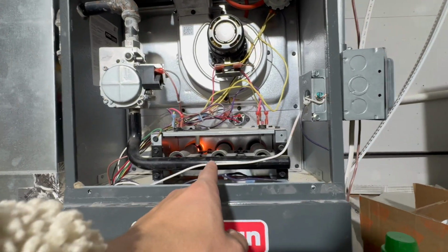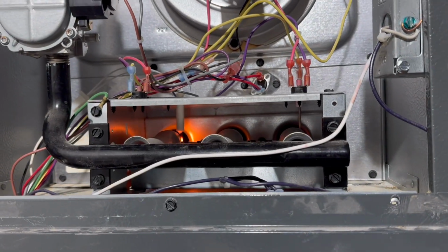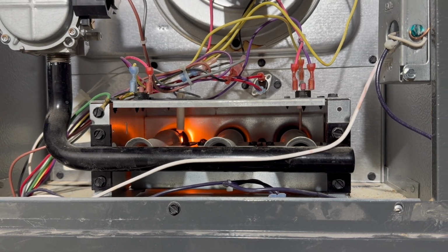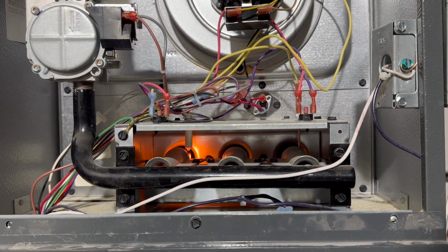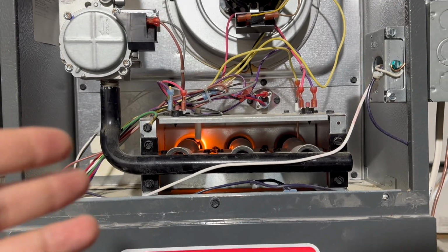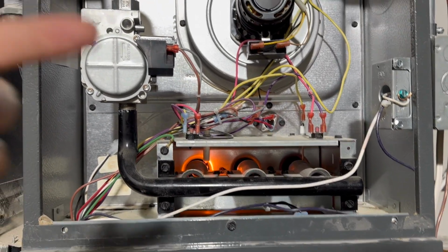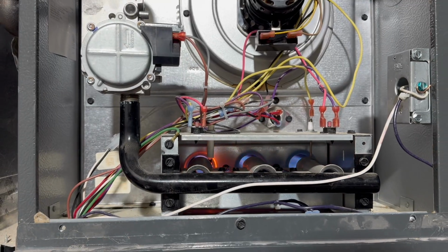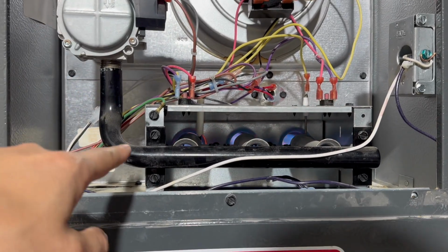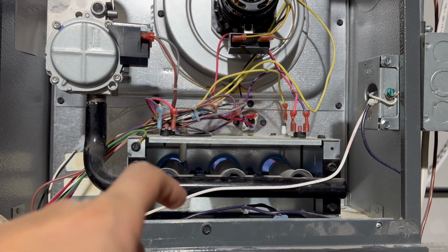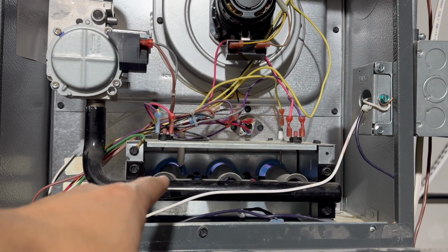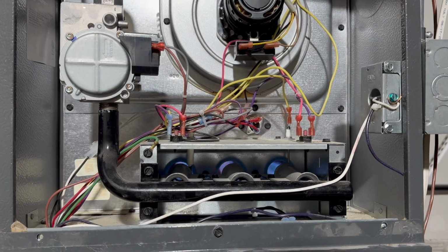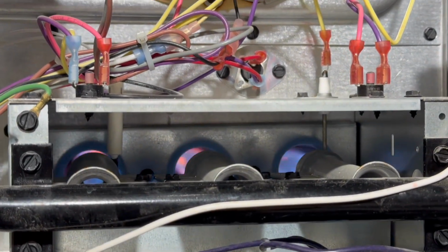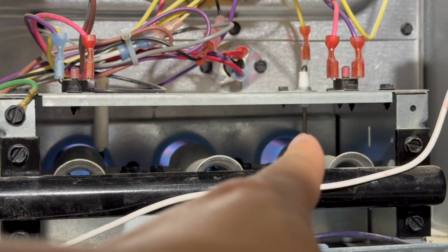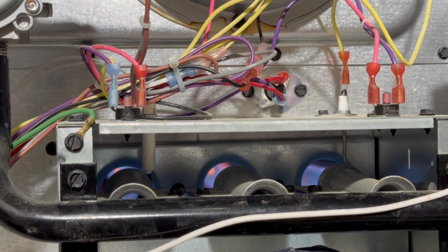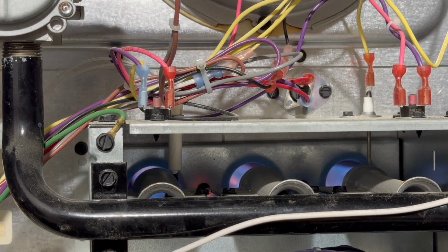You see the flame, the red flame over there. So that means it's heating up. Now it's going to wait for the gas to be released from here. Now it's released. So that means the gas is going through that flame, the igniter, and it's blowing. And now that sensor over there, the flame sensor, is saying, okay, we got the heat, everything is working fine, now just keep it constant.